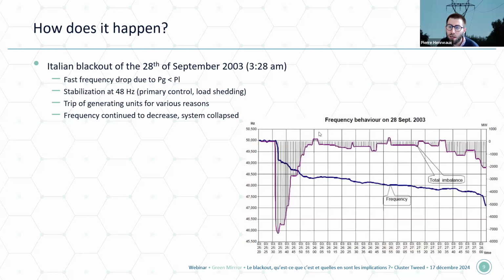Following that, Italy was, before the event, importing a lot of electricity. Suddenly, Italy was disconnected from the rest of the grid. So Italy faced an imbalance between the generation and the load, which means that they had a fast frequency drop following the disconnection because the load was much higher than the generation. And you see on this graph, on one side, the power imbalance. You see that the power imbalance following the split was around 7 gigawatts. And in blue, you have the frequency drop. So the frequency dropped quickly.